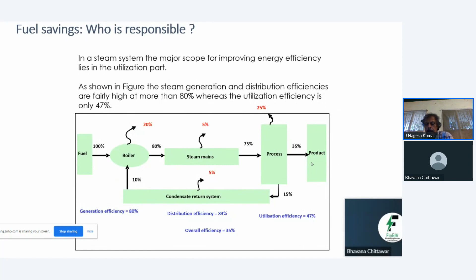If you look at the relative efficiencies, generation efficiency is 80%. Distribution efficiency from the boiler to the process is 83%. But utilization, 75 to 35, is only about 47%. That means there is a huge potential to save energy in the utilization phase. If you save energy here, then you reduce the fuel consumption in the boiler, because your steam consumption is reduced. So this should be the approach when you're looking to save fuel in the boiler. So it's not the boiler alone, but the end use.